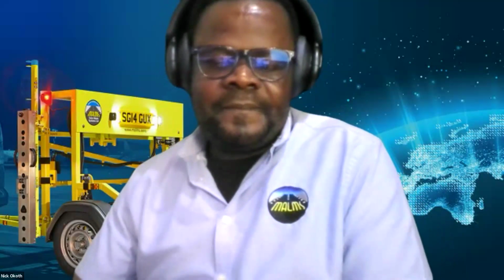So here, Nick, I think you're quite right in what you're saying, but the element of this question is associated with low insulation resistance values, and that brings us to another subject that we've already dealt with, rather than just the earthing network system. But the key issue is that to allow anyone near an AGL system who is an unqualified electrical person is fraught with danger. Yes, exactly. But I'm getting from this that how you implement an earthing system can compromise the insulation resistance under certain circumstances.